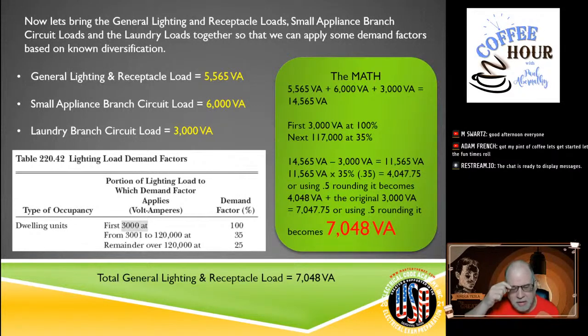In this case, remember that 3,000 VA, although it states it's for general lighting, is also covering the general use receptacle loads. So that's all covered in here, just making you aware that everything is covered within that. So now we're going to look at the table. I've got it on the screen so that you don't have to go to the code book if you want to stick right here.